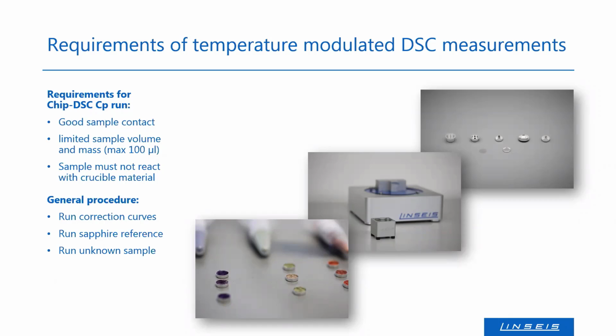What's also important is good sample contact, otherwise you cannot get the heat into the sample, and a limited sample volume to avoid temperature gradients. Our standard crucibles for the chip DSC, for example, the biggest crucible is around 100 microliters, so everything is okay then. But if you calibrate with a 0.5 millimeter calibration material and want to measure a 5 or 10 millimeter sample, for example a polymer with bad heat conductivity, then there will be an error. You have to make sure this doesn't happen.